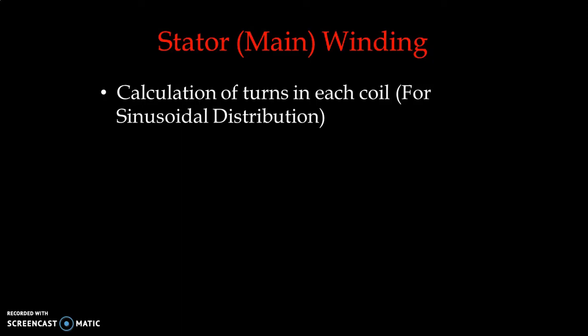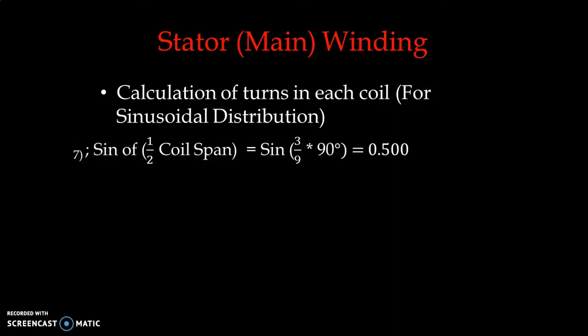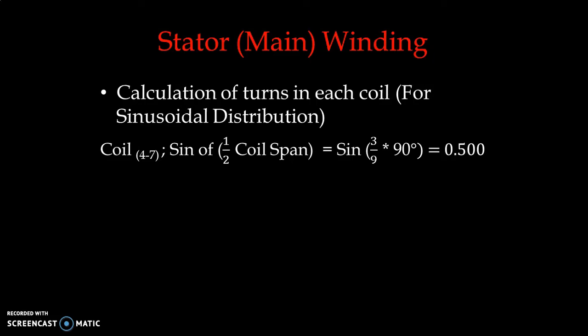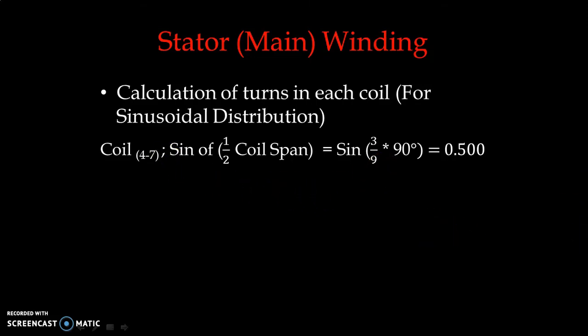We can see that each coil has a different span. Now, calculation of turns in each coil: we do this arrangement for a sinusoidal distribution of the magnetomotive force wave to get very close to a sine wave. For coil 4-7, the innermost coil, we take the equation as sine of half of the coil span. For coil 4-7, sine of (3/9 × 90°), which comes to 0.5.